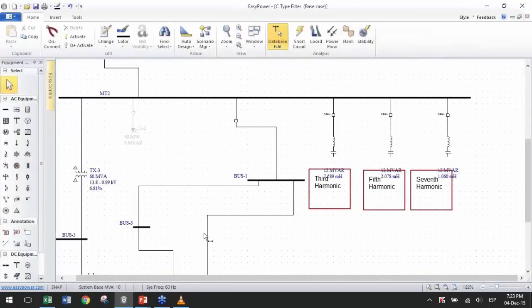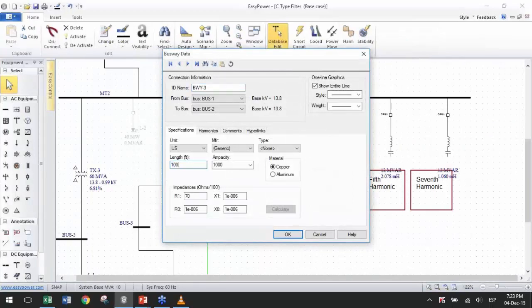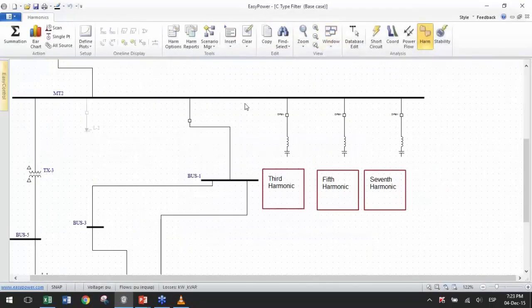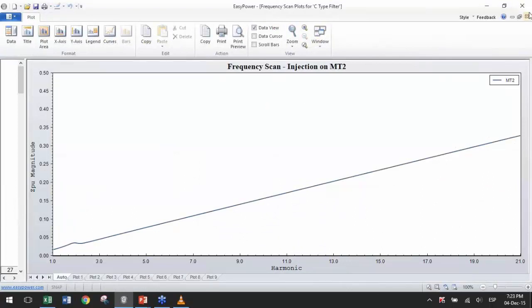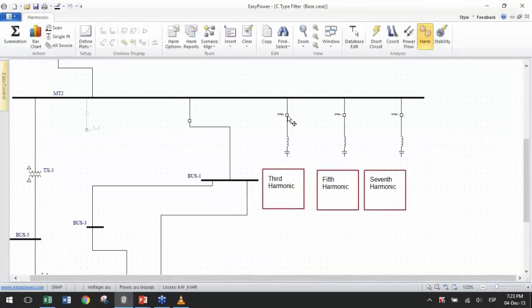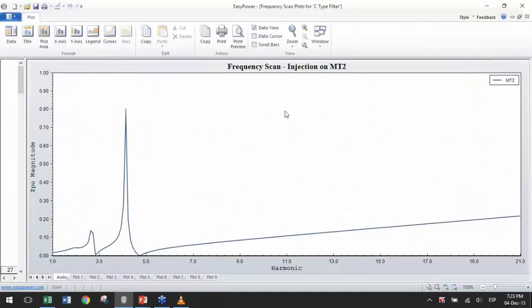Now, this value, I think, should be lower. Let's see. So the filter is working great. Now, what happens when I add the other filters? Let's say the third and the fifth harmonic. I have the resonance from the fifth harmonic filter, the resonance from the third, but on the second harmonic, which is the one I really care about in the arc furnace facility, I have no resonance. Therefore, I will not have second voltage harmonic distortion.